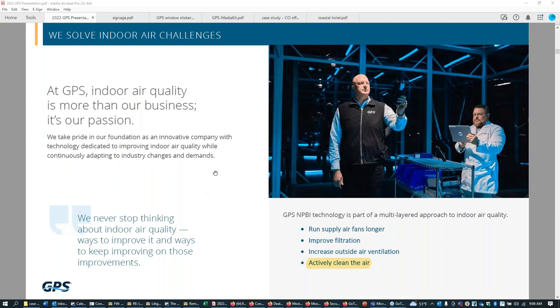And ASHRAE said at the beginning of the pandemic, run your HVAC systems longer, purge your buildings before and after occupancy. That will allow the filters to grab more out of the air, and it will allow your outside air to dilute any potential pathogens inside the building.